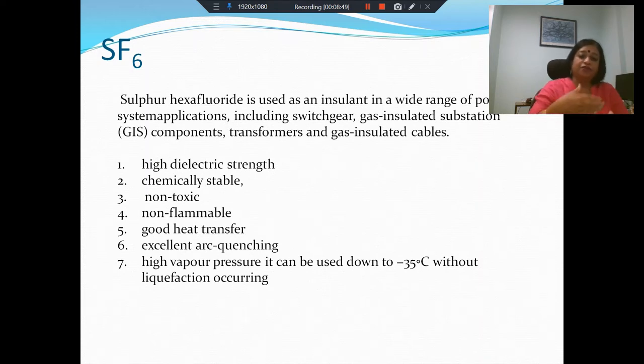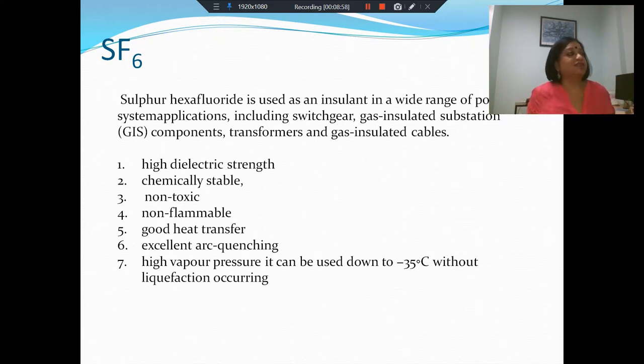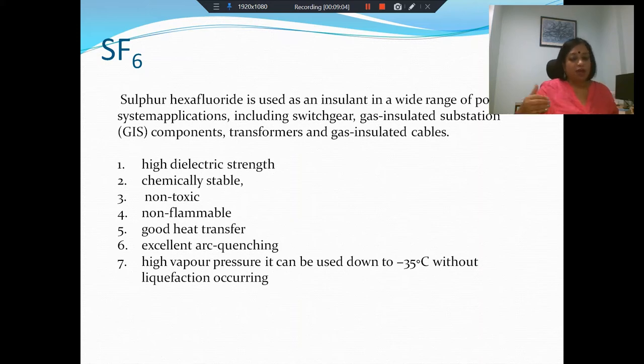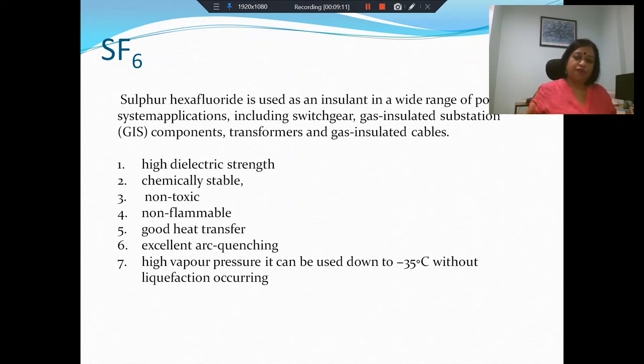SF6 has good heat transfer capabilities and, as already mentioned, excellent arc quenching capacities. Another important thing is it has a high vapor pressure, so even when we go down to pretty low temperatures, it remains as a gas and does not become a liquid. A gaseous insulating medium has certain advantages — it can fill up the entire space available with no gaps remaining.